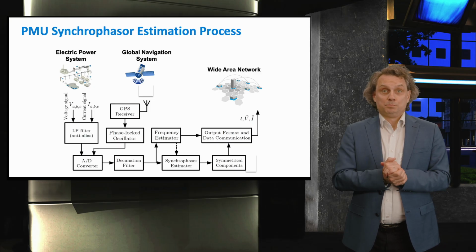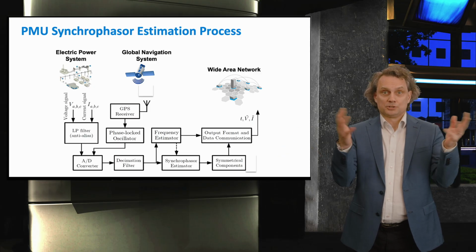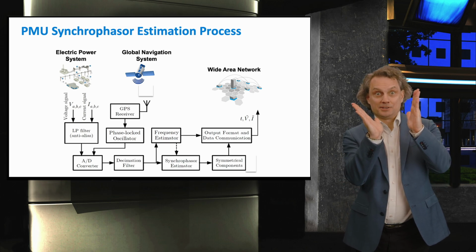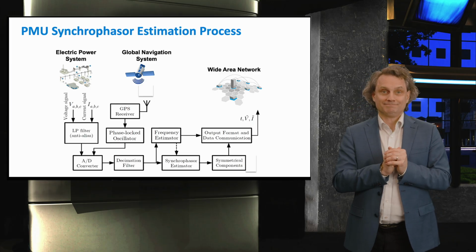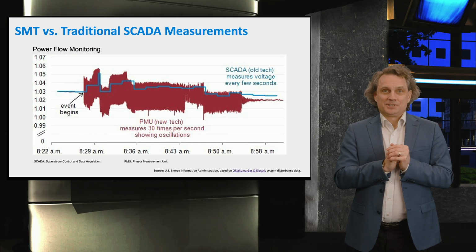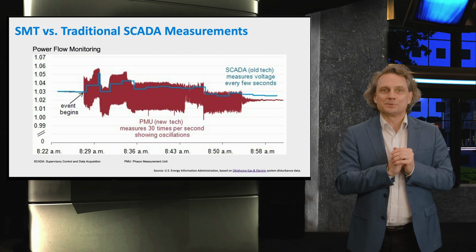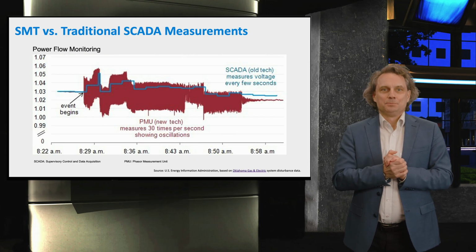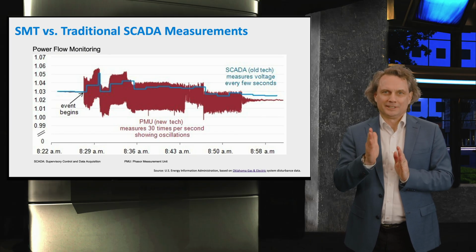When we receive such PMU streams from all substations, we can see which phasors are aligned, what is the phase difference, and also if some phasors are moving. Besides the nifty concept of using phasors instead of physical sample snapshots, PMU have another advantage. Their much higher reporting rate.